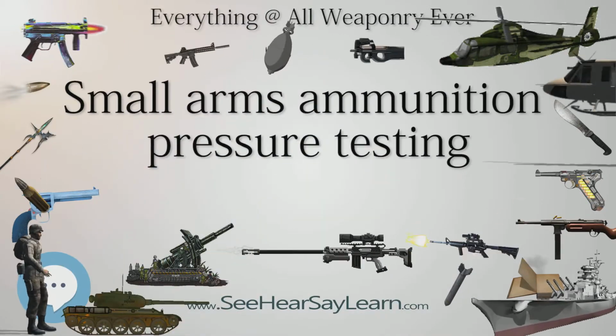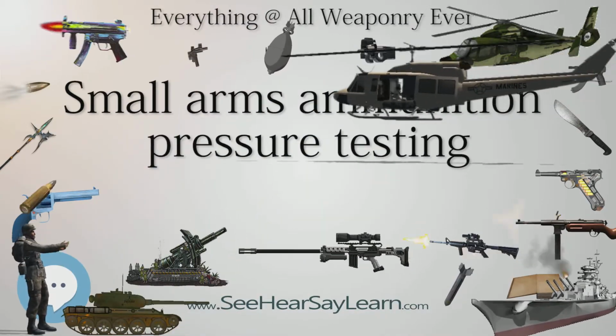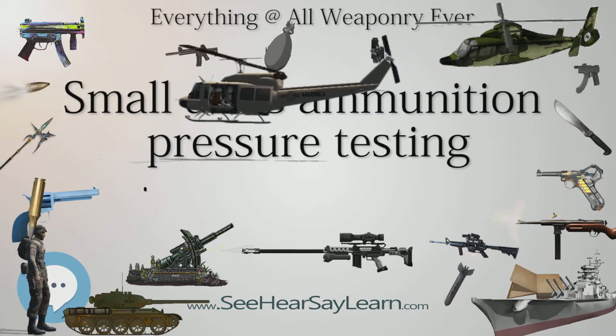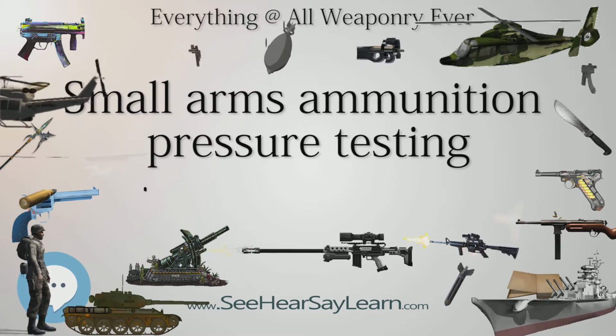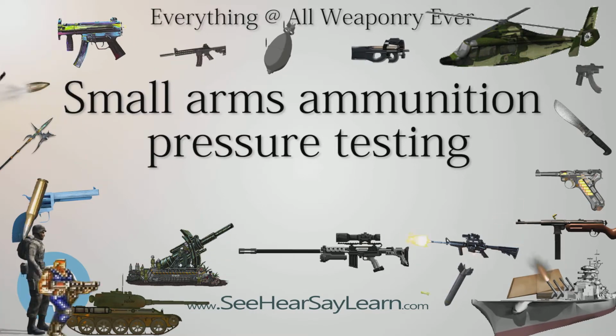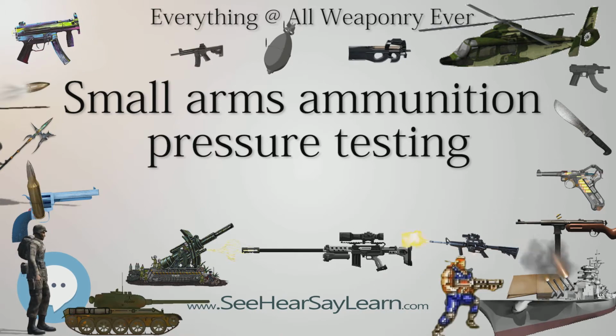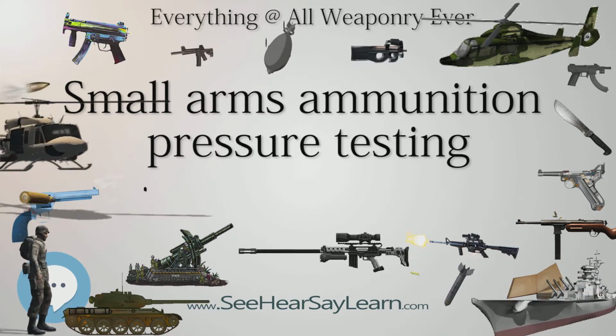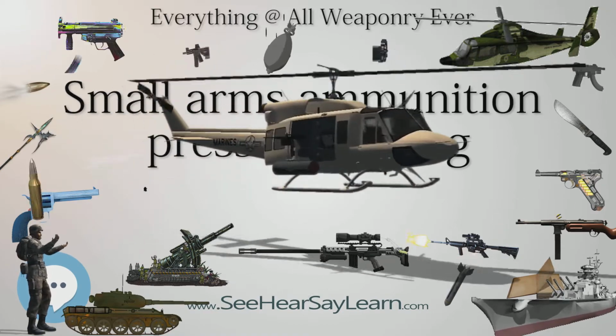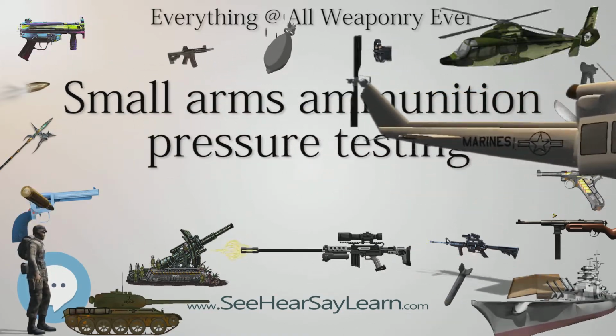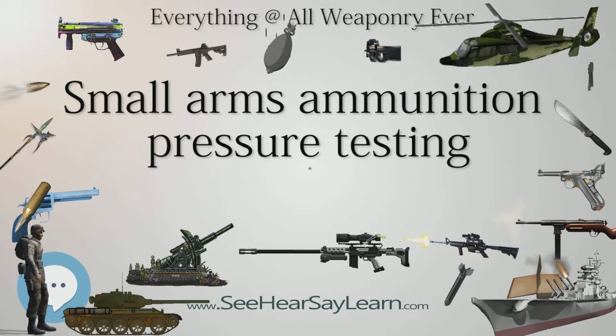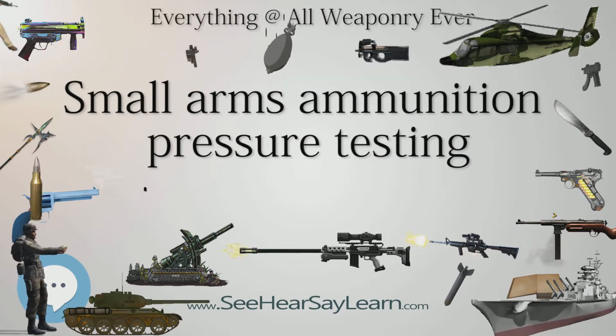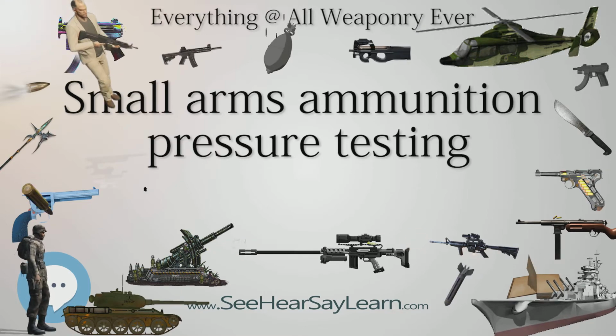The disadvantage of this mount is that the pressure rises much faster than in a drilled cartridge case. This causes high-frequency oscillations of the pressure sensor, approximately 200 kHz for a Kistler 6215 transducer, and this requires electronic filtering, with the drawback that filtering also affects the lower harmonics where a peak is found, causing a slight error in the measurement. This slight error is not always well mastered, and this causes a lot of discussion about the filter order, cutoff frequency, and its type, Bessel or Butterworth.